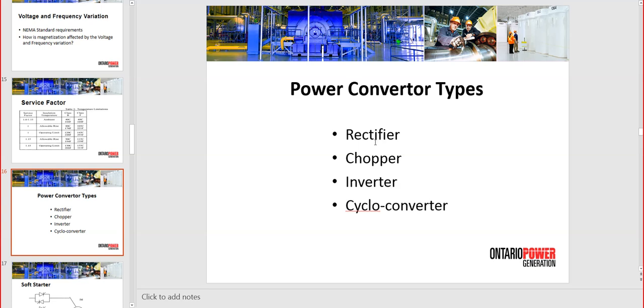So when we have a VFD, we will use 2 out of these 4 converters at the same time. It's a double stage converter. We will have a rectifier that takes the AC input to a DC bus. The DC bus will have a capacitor bank, and the capacitor bank needs to be proportional with the power. And then we will have an inverter taking that DC back to AC and supplying the variable frequency and variable voltage. At the same time, the inverter will change voltage and frequency on the motor input. And yes, you need filters and you need to take care of the harmonics.